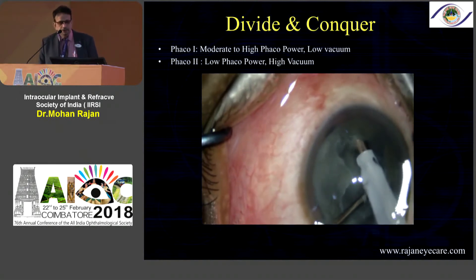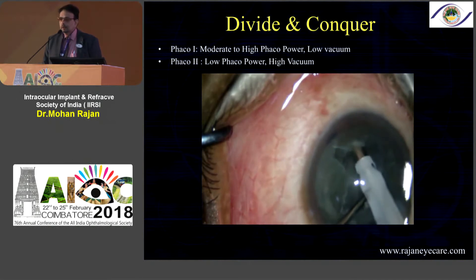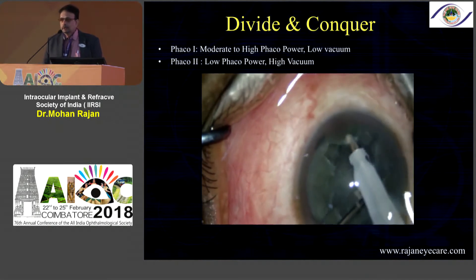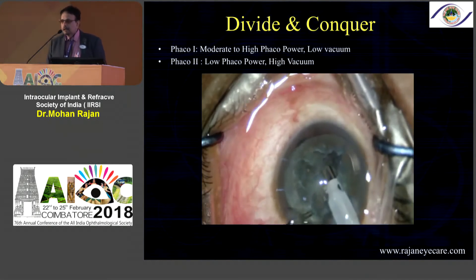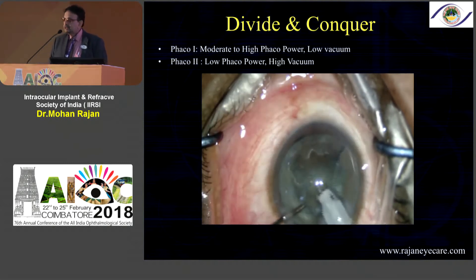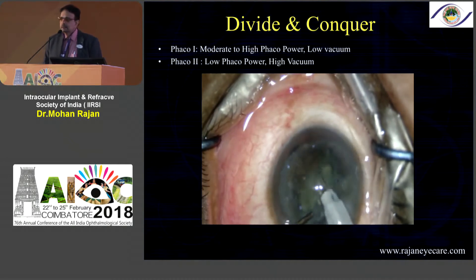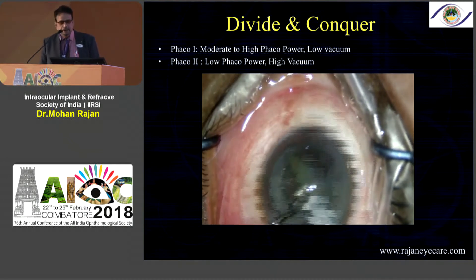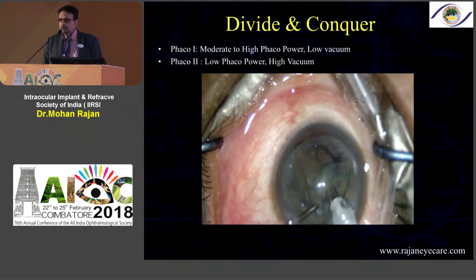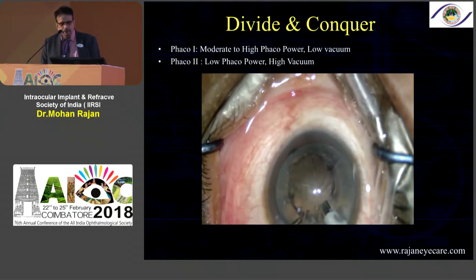With four quadrants, you use high aspiration flow rate to increase followability and high vacuum to increase holdability of the nucleus. The downside is that in harder cataracts, divide and conquer takes a lot of time and can consume a lot of phaco energy, which can be detrimental to the corneal endothelium.